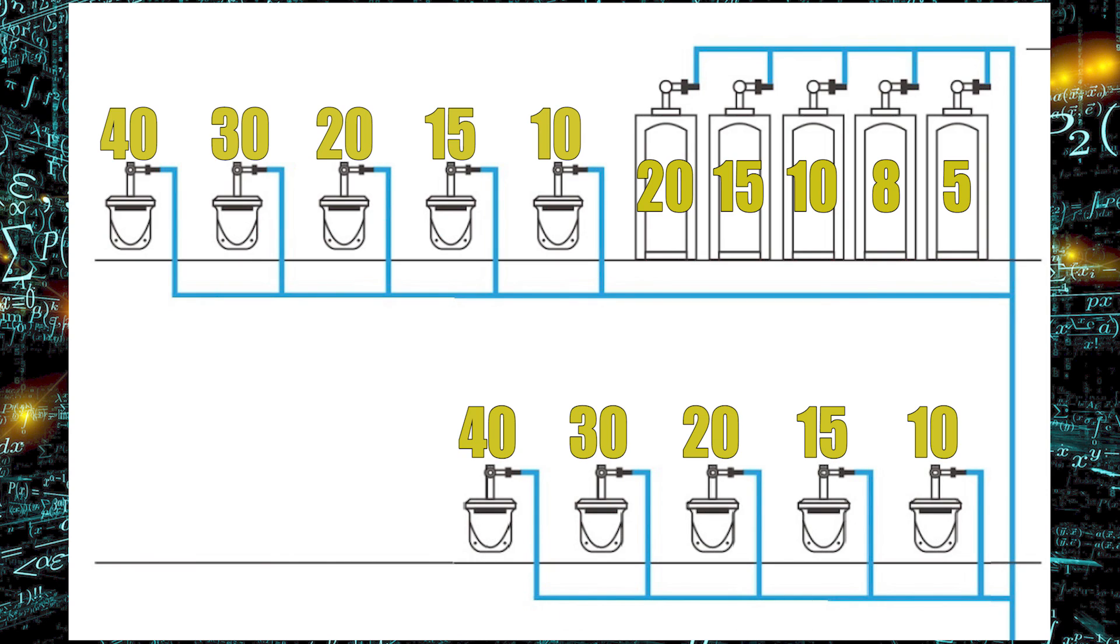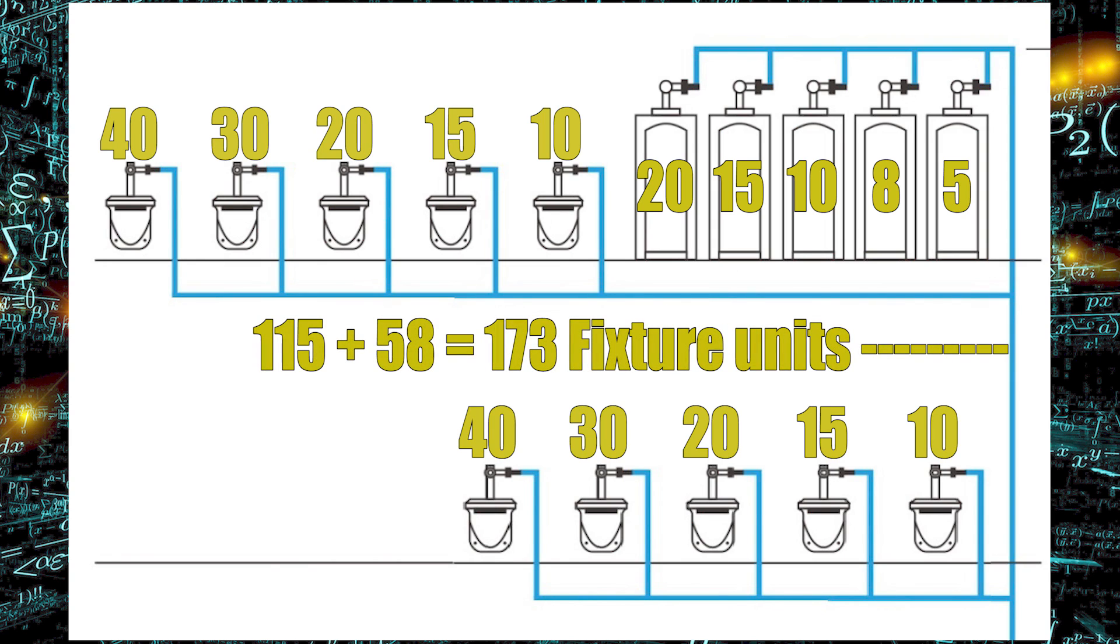Now the upper floor is not going to be anything special. Looking at the water closets, we start at 40, then we have 30, 20, 15, and 10. The urinals, once again, 20, 15, 10, 8, and 5. So we're just going to add all those up for this common pipe down here, and we're going to get 173 fixture units right there.